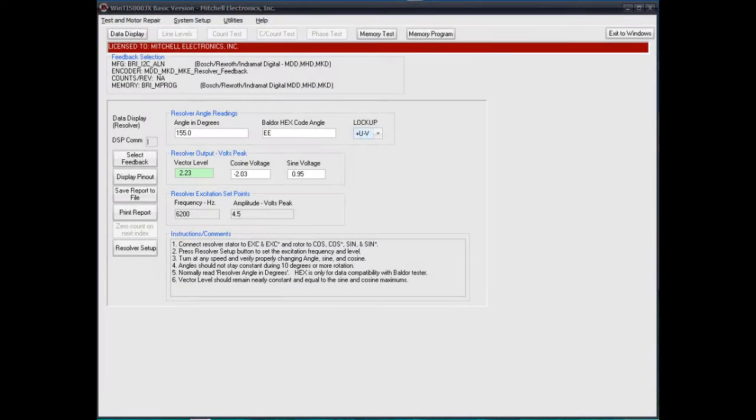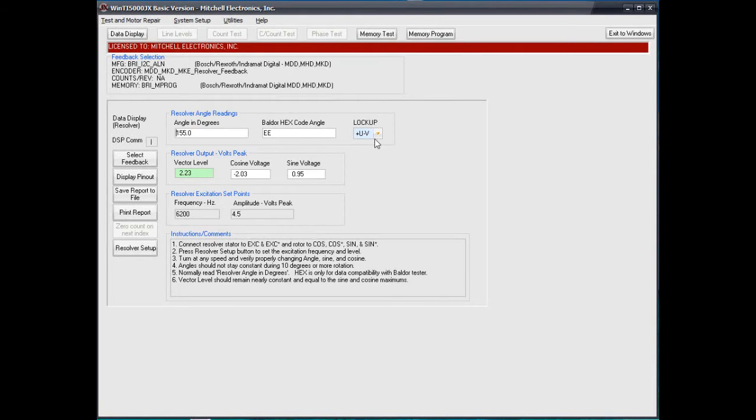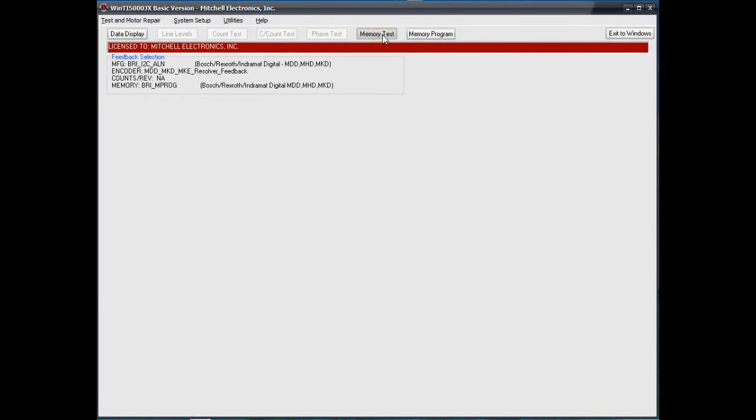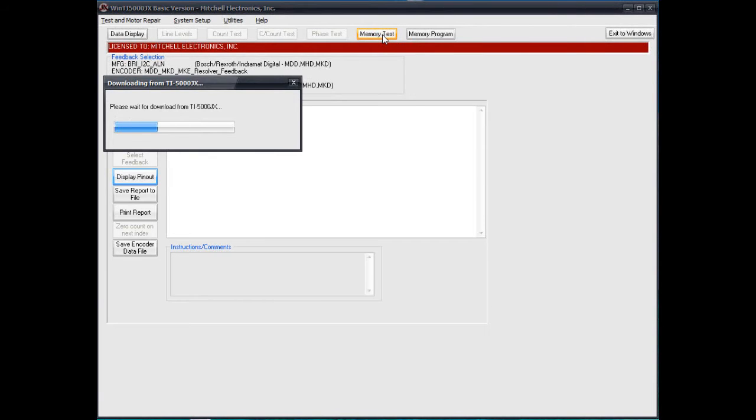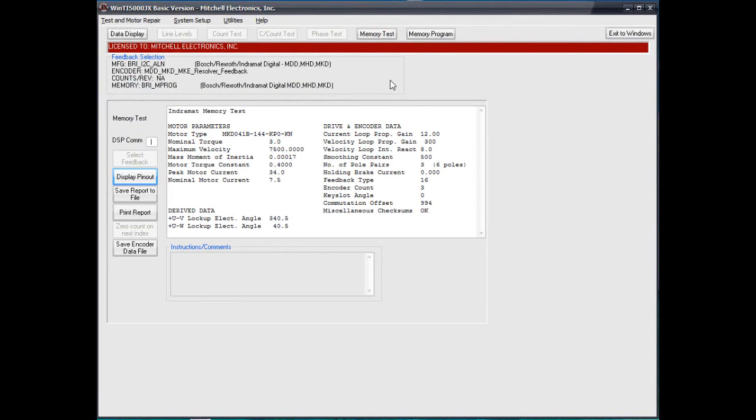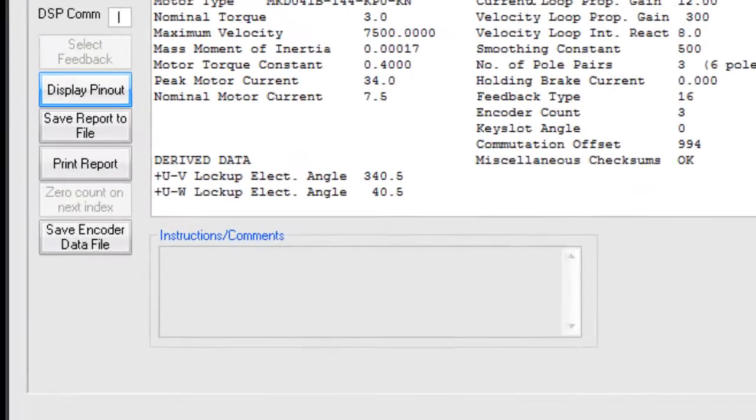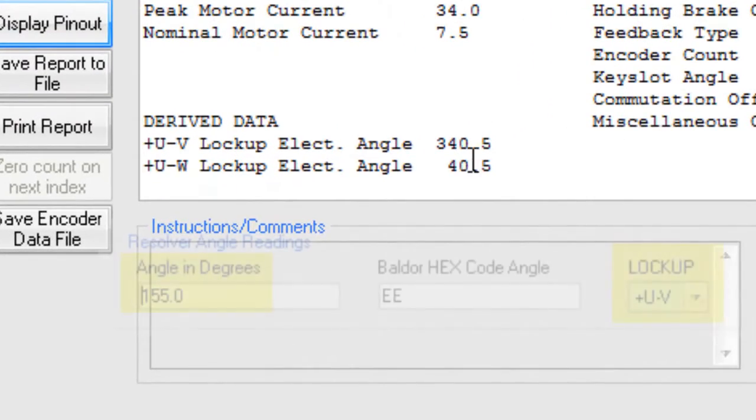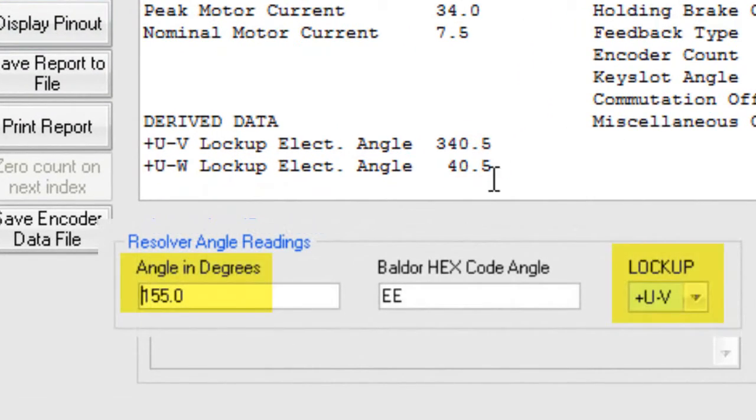In this example, we have recorded the alignment of the resolver feedback on an Indramat MKD motor after it had recently been repaired. However, the angles stored in the memory data do not match our current alignment and that will cause errors on the drive.